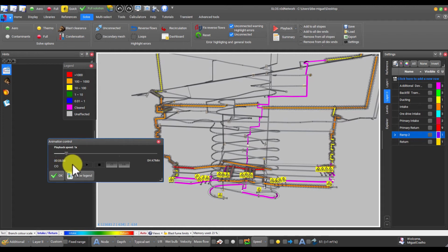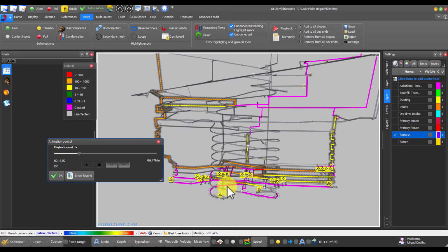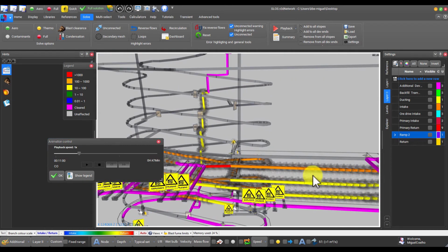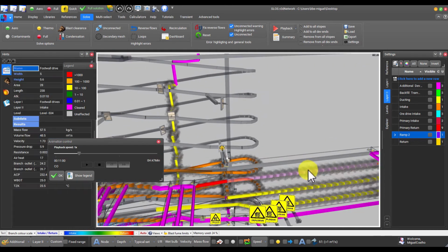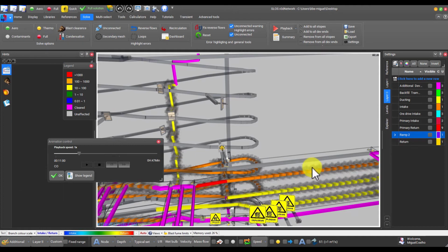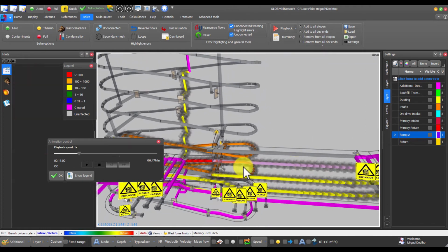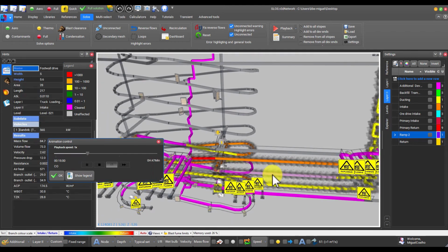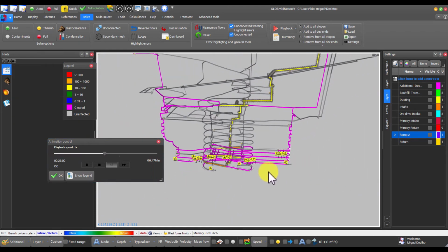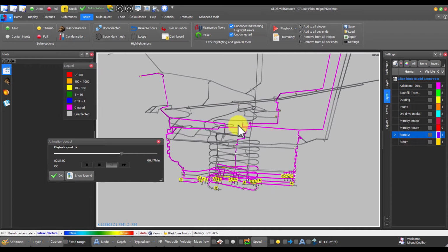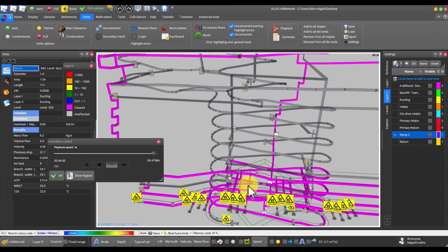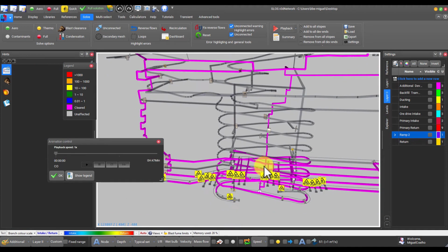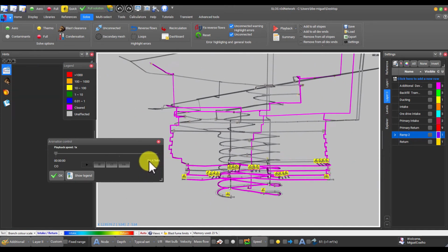And as the playback plays, you can see how blast clears. You can also see the branches that are still with contaminants have this graphic rendering around it. Then you can see it clearing. There it goes, just the return. And you have this little trail here taking its time to clear, which you can go troubleshoot if you want to improve your blast clearance time. Maybe you're trying to target 45 minutes or half an hour.